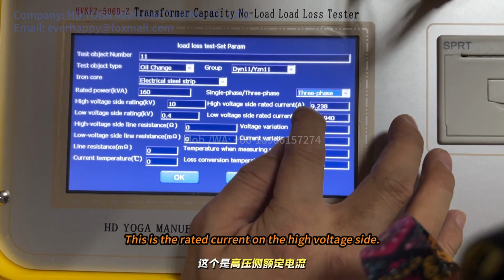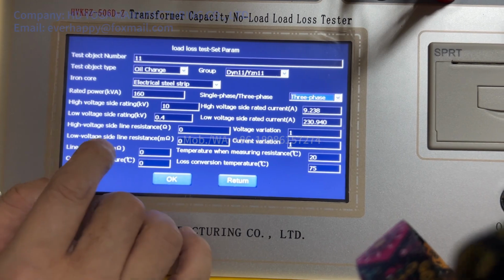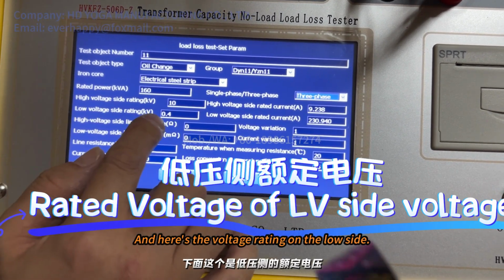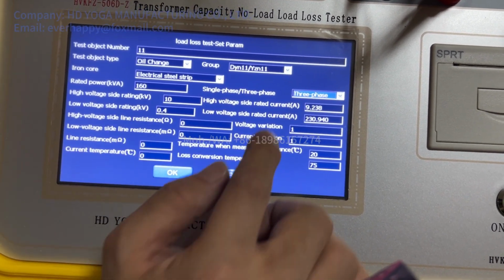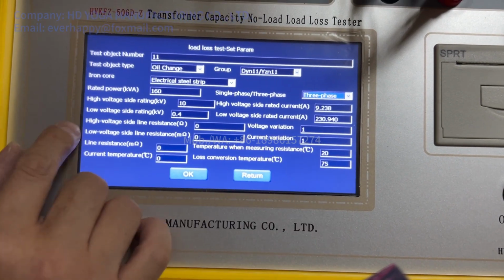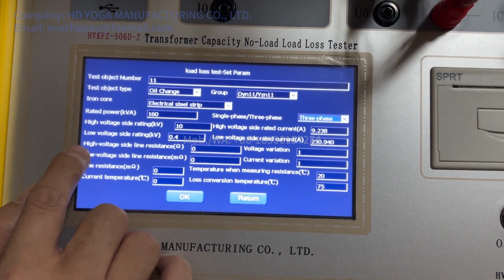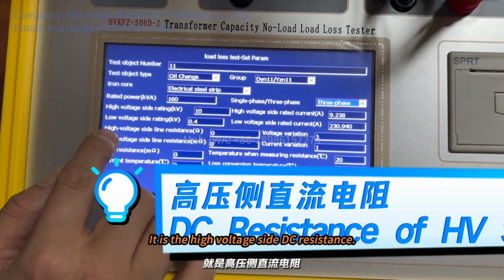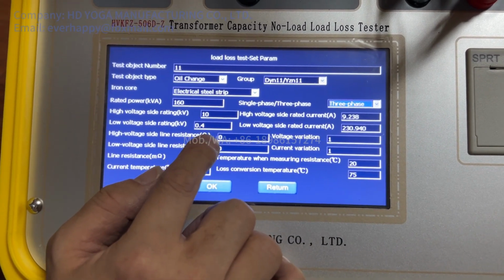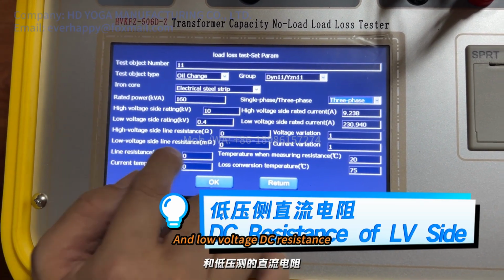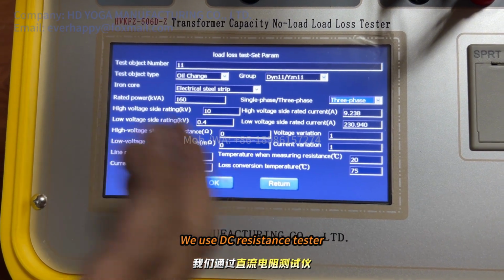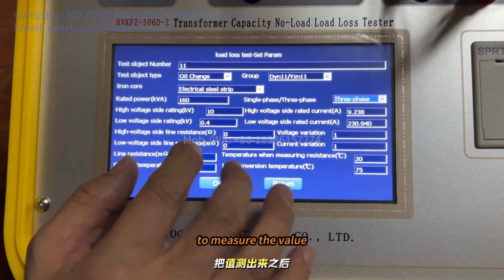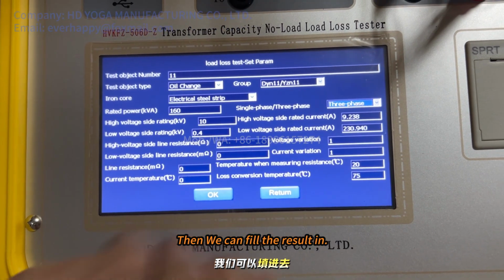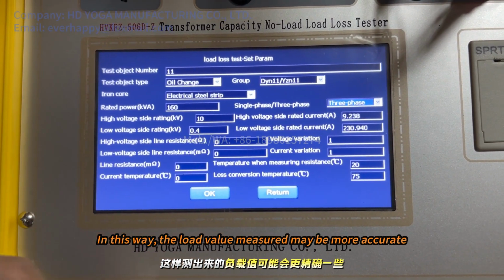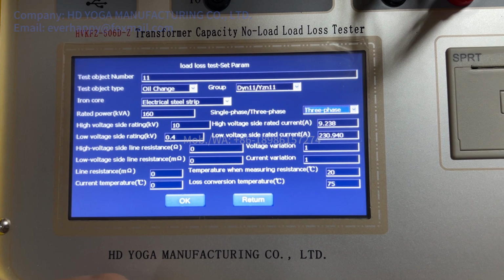This is the rated current on the high voltage side. And here is the voltage rating on the low voltage side. Low voltage side rated current. This is an important value when we do the load test. It is the high voltage side DC resistance and low voltage side DC resistance. We use a DC resistance tester to measure the value. Then we can fill the result in. In this way, the load value measured may be more accurate.